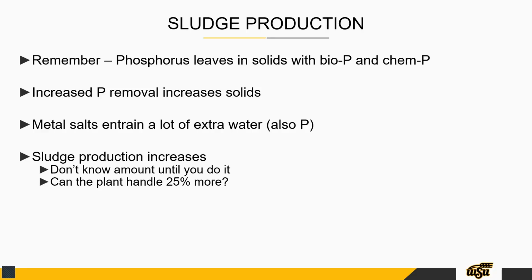I've had operators ask me, and I've not ever found a straight answer. But the WEF type of literature out there says about a 25% increase is what you should plan for. Some facilities, that's not going to be an issue. Some of them are going to quickly have issues with biosolids operations.